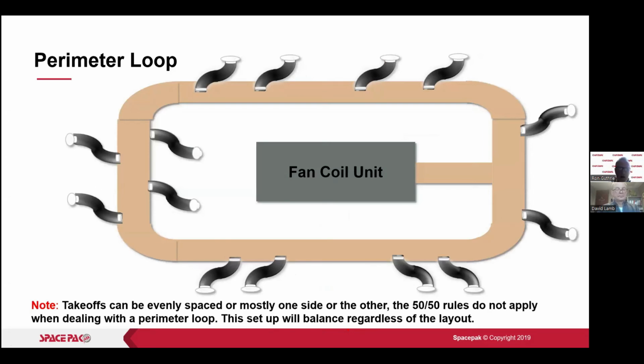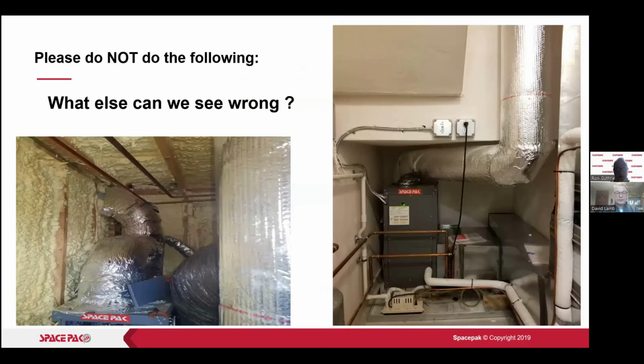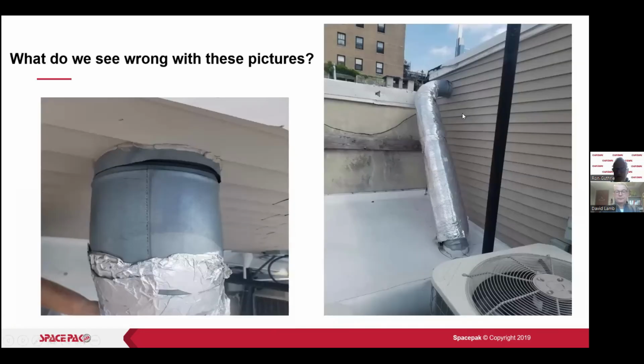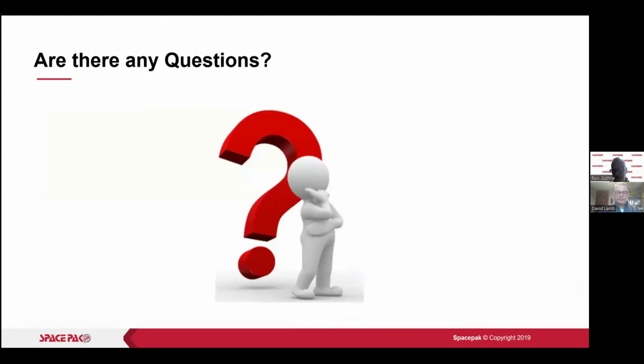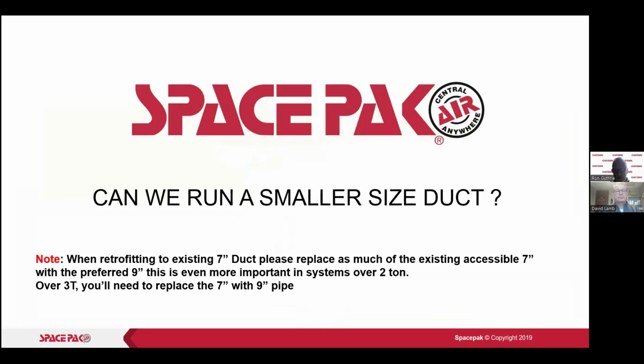All right, perimeter loop, as I said before, it equalizes. So this is a good way to do it if you can do it this way and not end up with too much duct. These are a couple of things that were done wrong. We didn't come out of this unit with 18 inches before we had a fitting. This was a vertical unit. Same here on this unit as well. This is another thing on that one job: they came outside, ran down, and didn't adequately insulate. So that was not a very good job that they did for other reasons as well.